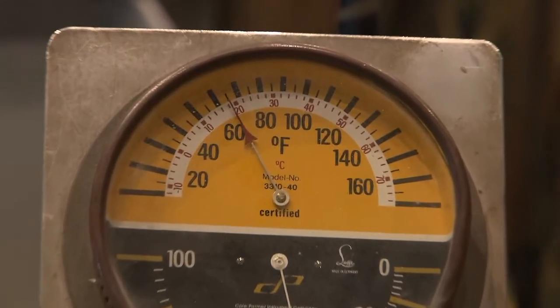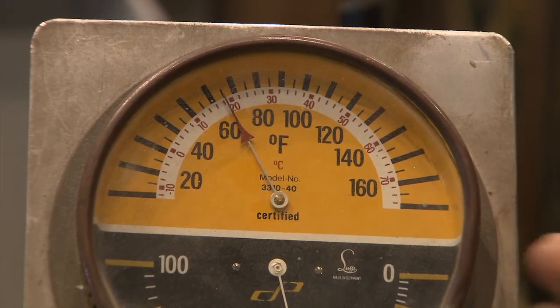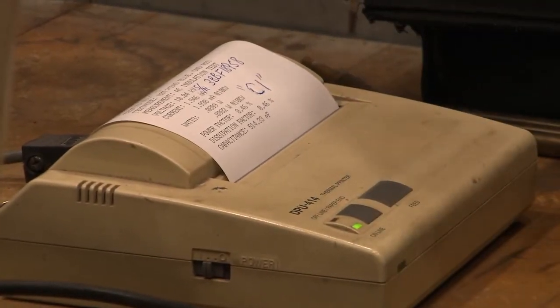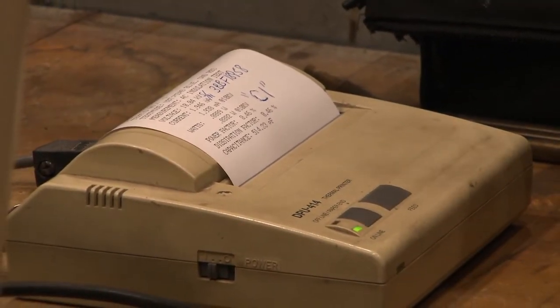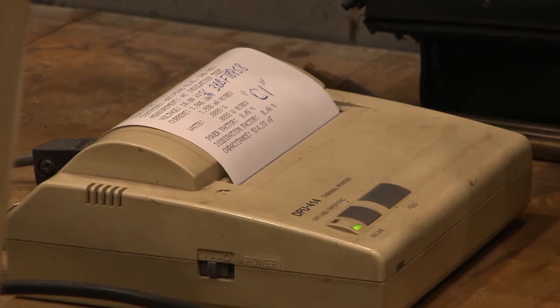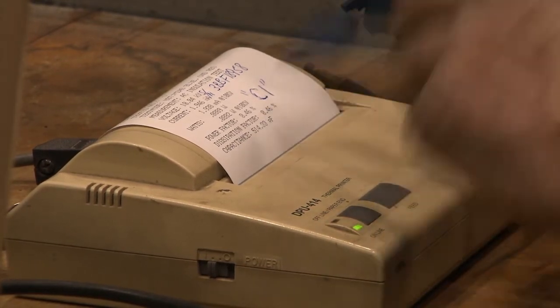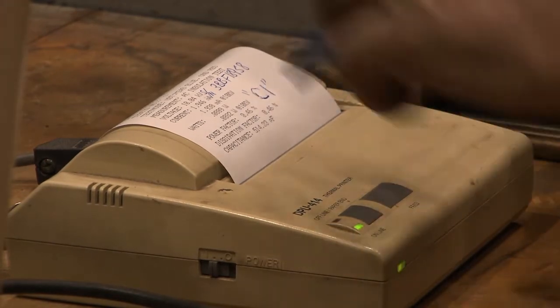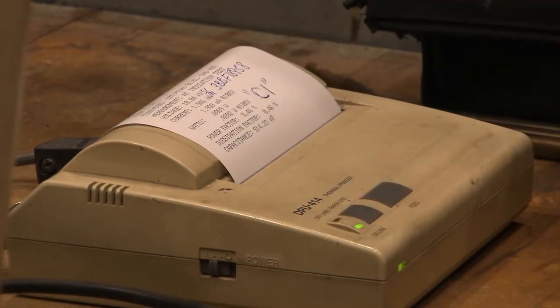The results of the C1 test can be printed out, and because the tests are conducted using much higher voltage, the results are much more accurate than the results from the first C1 test conducted at 40 volts. In this case, the results indicate that the bushing is in very good condition.